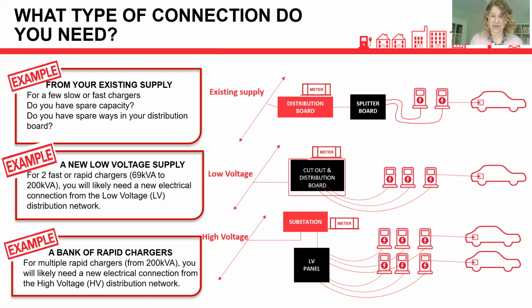Now, in the case of a new connection, be it low voltage or high voltage, you can either have a standalone connection for your EV chargers only, or you may wish to incorporate your other site load onto that and disconnect your existing supply. The one thing you cannot do is have two supplies into the same building.